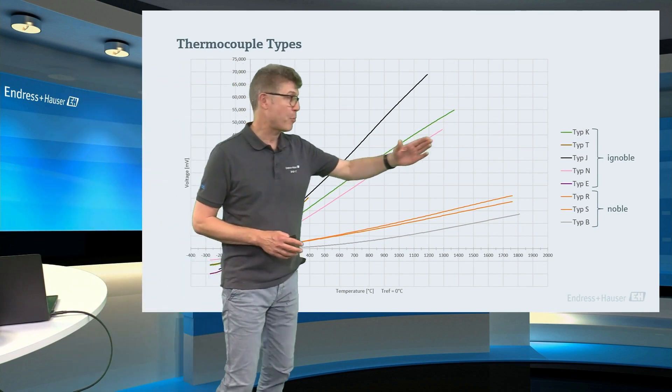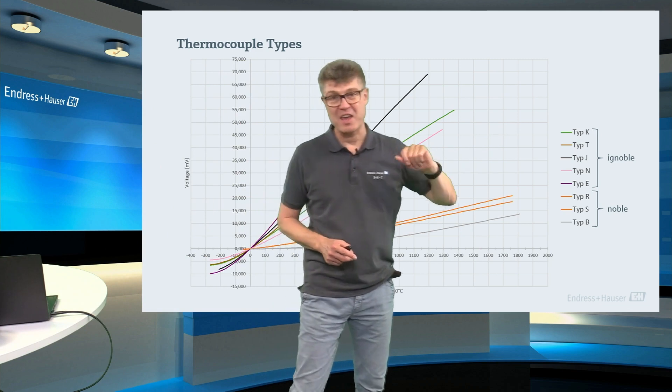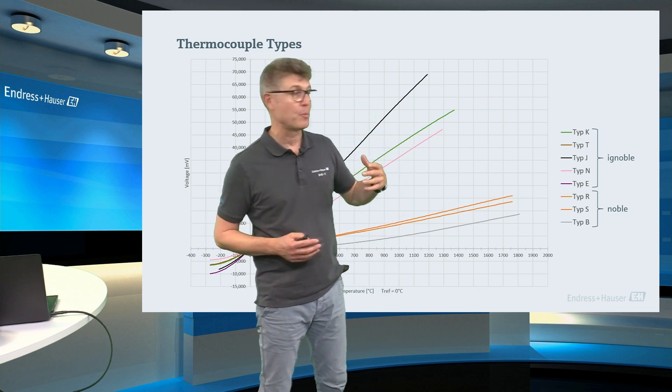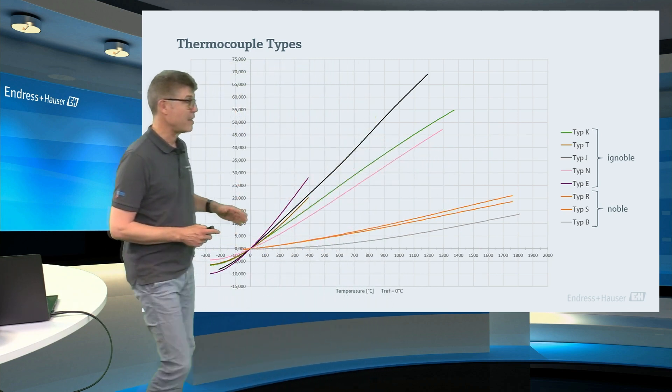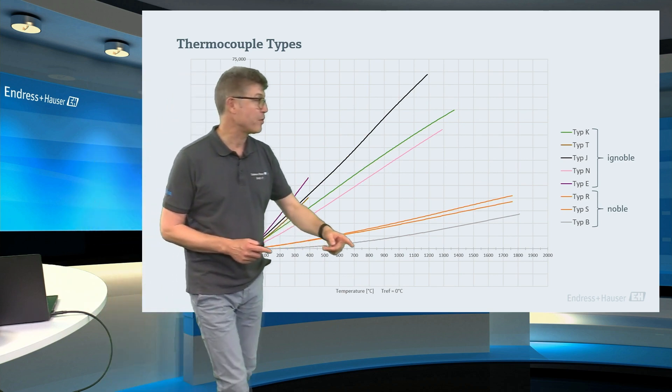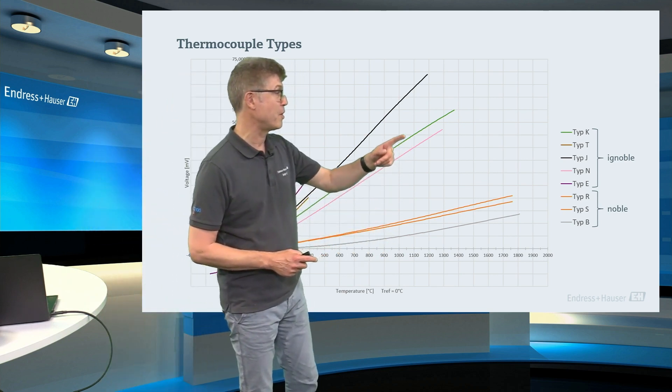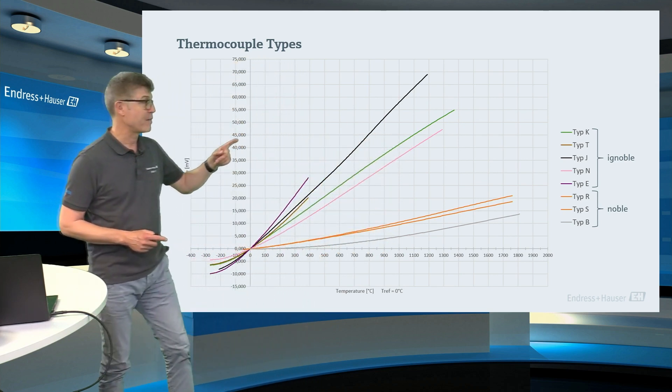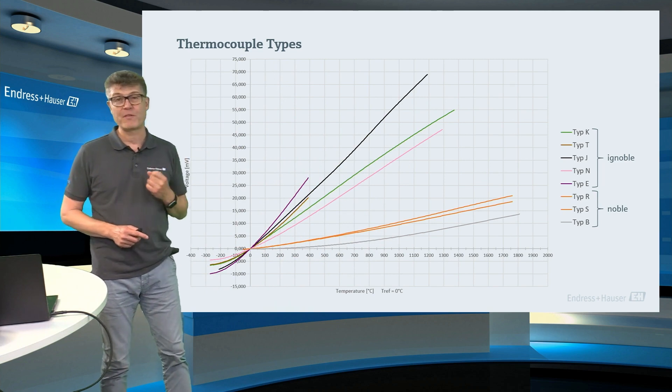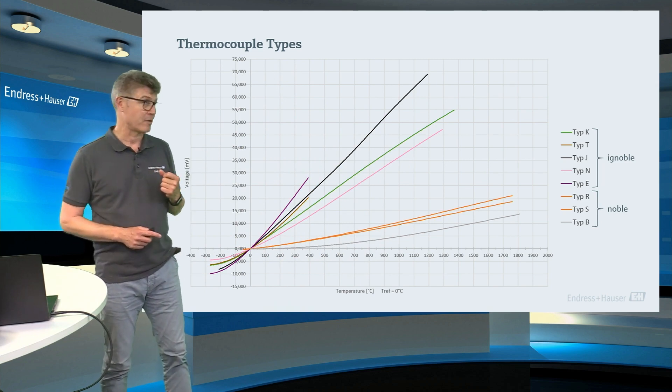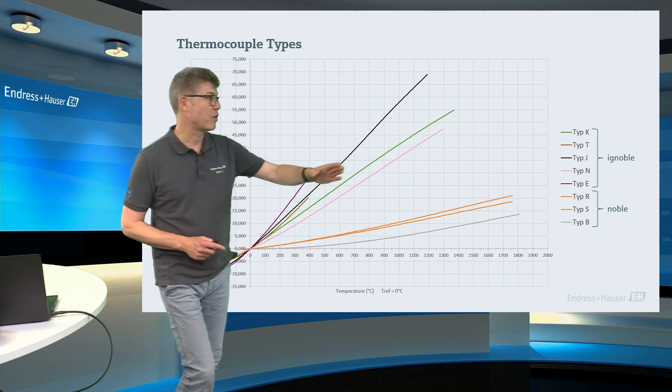The most popular one is called type K, which is nickel-chrome-nickel. And you see here, at 1000 degrees of temperature difference, we will have a signal of 45 millivolts. And, yeah, this looks quite linear.